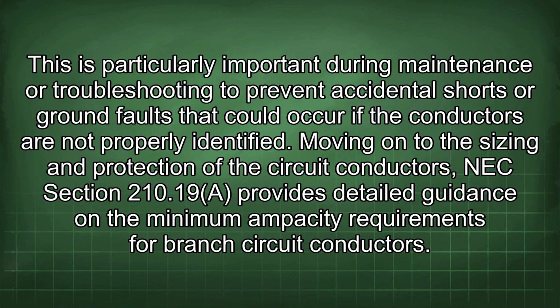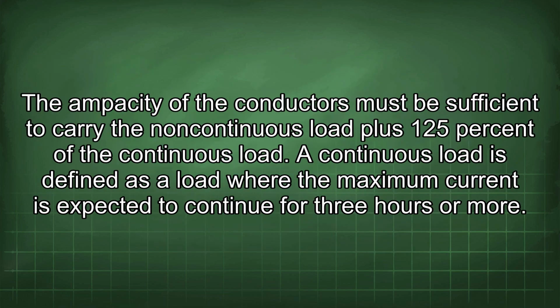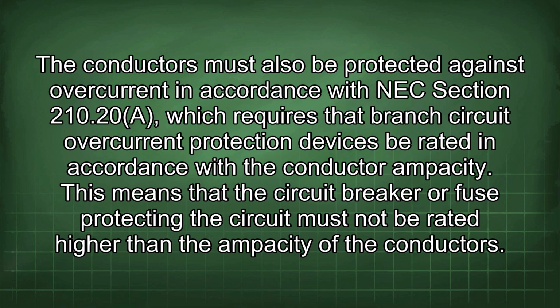Moving on to the sizing and protection of the circuit conductors, NEC Section 210.19 provides detailed guidance on the minimum ampacity requirements for branch circuit conductors. The ampacity of the conductors must be sufficient to carry the non-continuous load plus 125% of the continuous load. A continuous load is defined as a load where the maximum current is expected to continue for 3 hours or more.